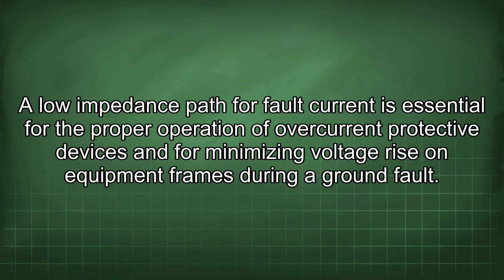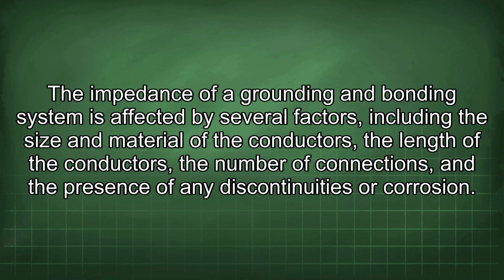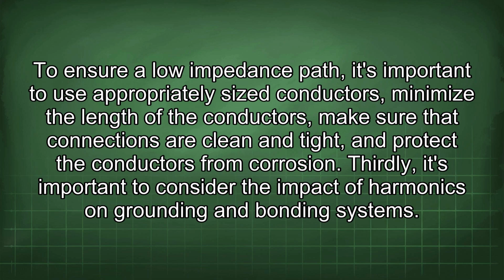A lower impedance path for fault current is essential for the proper operation of overcurrent protective devices and for minimizing voltage rise on equipment frames during a ground fault. The impedance of a grounding and bonding system is affected by several factors, including the size and material of the conductors, the length of the conductors, the number of connections, and the presence of any discontinuities or corrosion. To ensure a low impedance path, it's important to use appropriately sized conductors, minimize the length of the conductors, make sure that connections are clean and tight, and protect the conductors from corrosion.